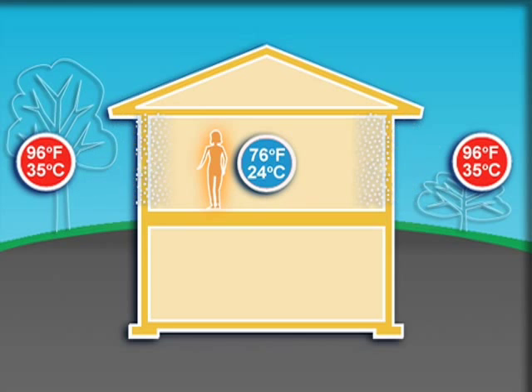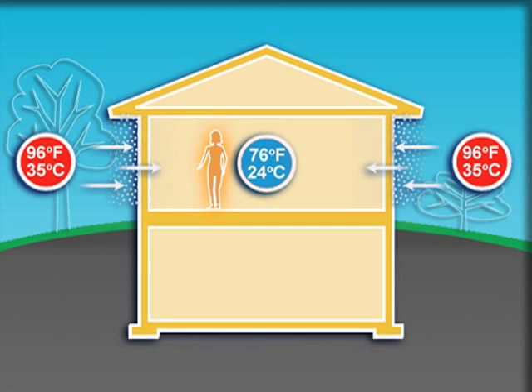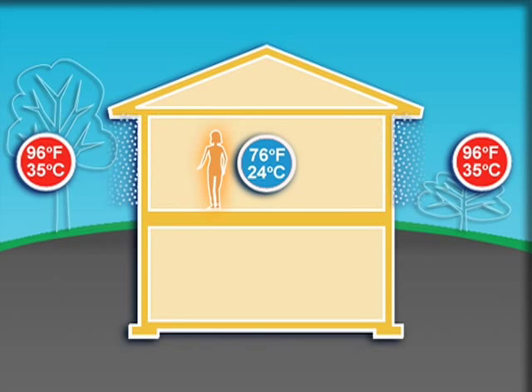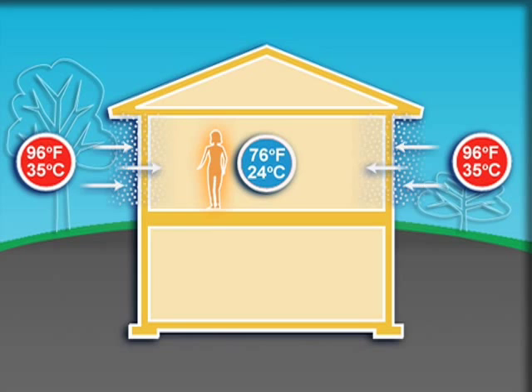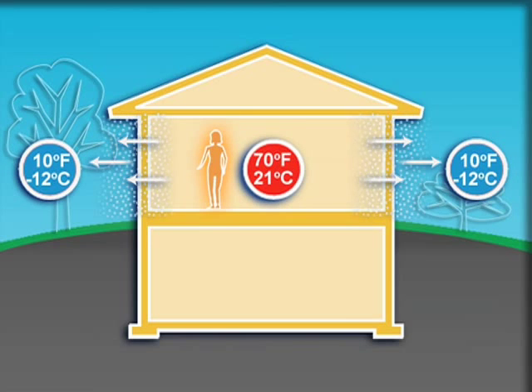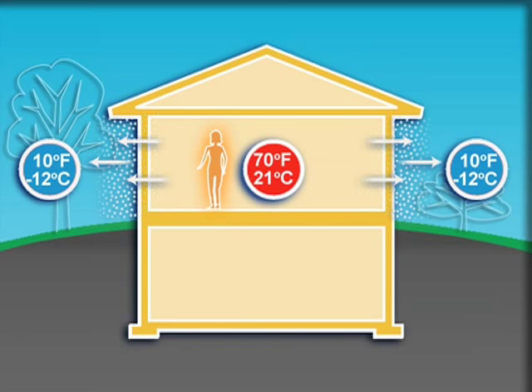The flow of water vapor occurs when a difference in humidity is present. For example, on a hot humid day, when the air conditioner is running, it is both cooling and dehumidifying the interior. This difference in humidity levels between outside and inside creates a flow of water vapor from the outside in. On a cold day, the flow of water vapor will move from the indoors to the outdoors when the relative humidity is higher inside.